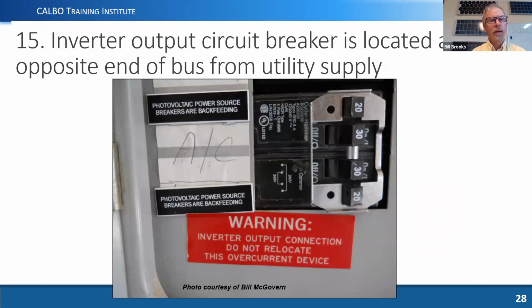An inverter output circuit is located at the opposite end of the bus from the utility supply, and this is not a general requirement. This is just if you're using the 120% rule, which has historically been a very common option used to interconnect the solar to a house. Then we'll have this sign that says don't relocate the overcurrent device, asking you to put it at the opposite end from the utility supply.